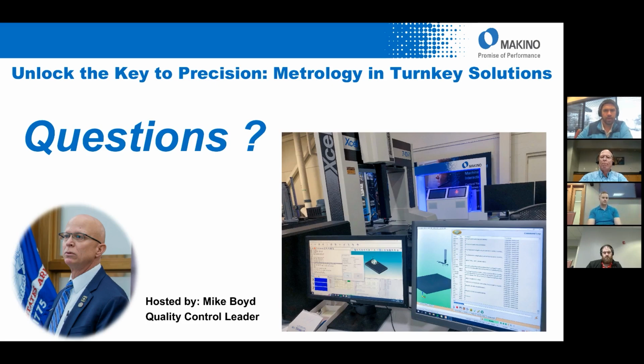Thank you. The general rule of thumb for correlation studies, or even for the gauge R&R we talked about in the video, is 10% of the total tolerance. For example, if you've got a 100 micron true position tolerance, you want the measurable amount we get here compared to at the customer to be less than 10% difference — so less than 10 microns difference between what they measure and what we measure. That's a good general rule of thumb. For a feature with a tighter tolerance, that number shrinks, and if the tolerance is bigger, say 500 micron true position, you have a bigger range. So that's usually the good rule of thumb to follow.